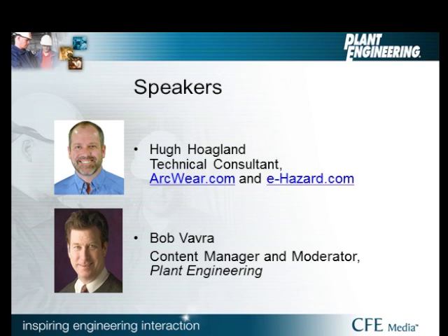Good preventative maintenance and proper device coordination will make your plant more reliable, and the after effect is that it actually makes it safer from an arc flash perspective. We can't look at any of these issues around electrical management within the facility as single issue items. They're all interrelated and very important to the overall safety, health, and profitability of the facility, and those are things that plant engineering readers care a great deal about.